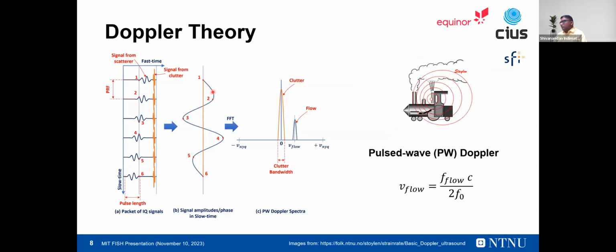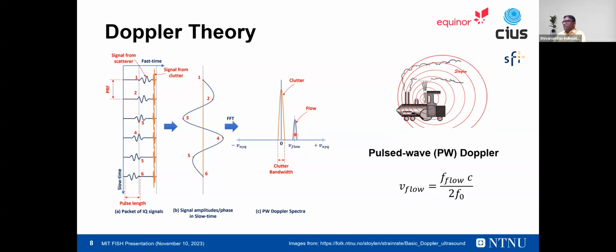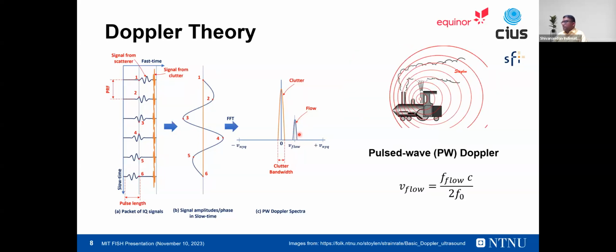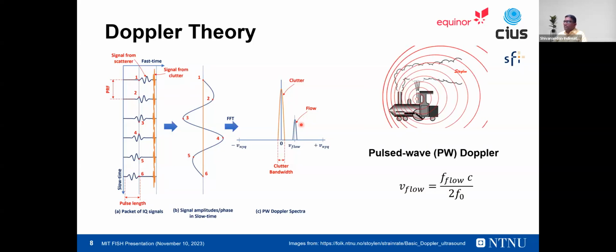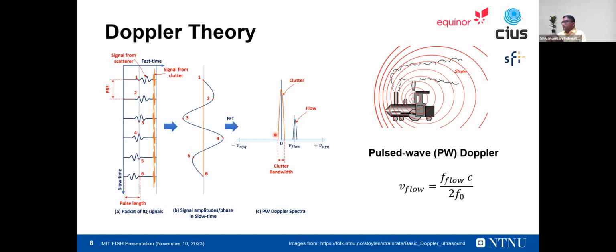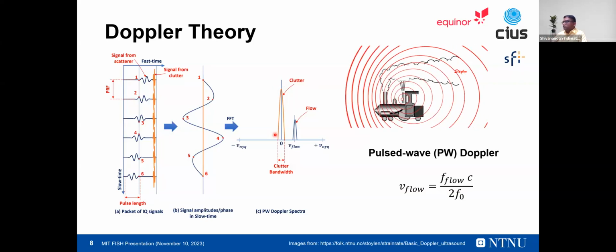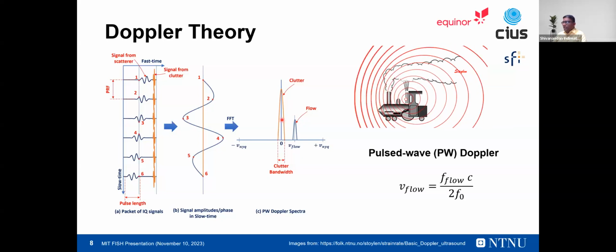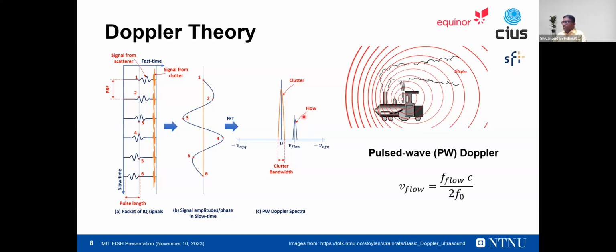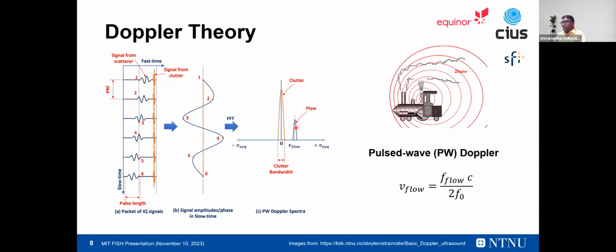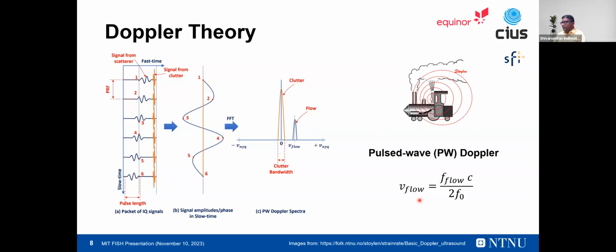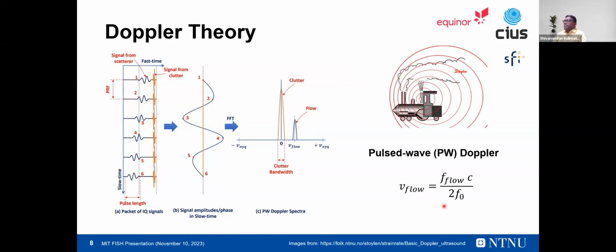And then we quantify the phase shift for each depth that we're interested in, or each sample volume. If we look at that phase shift in the Fourier domain, or the frequency domain, then we can identify high frequency components which are attributed to the fluid flow because of these backscatter signals. You also have some low frequency components which might be because of stationary objects in the environment, also lateral flows, etc., which we call clutter, and we try to filter it out. But then using the high frequency flow components, we can calculate fluid flow. It's pretty basic in that sense.